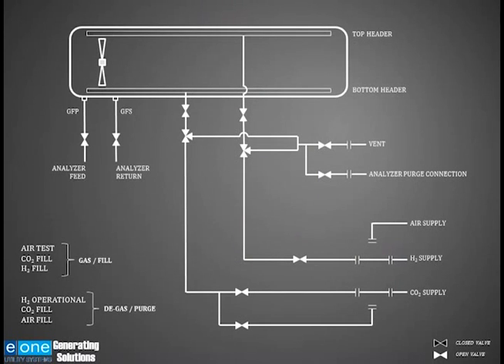Now I'm going to go through the purging process of the generator, and we'll make an assumption here that this generator was just worked on and it's got air in it, and now we want to put hydrogen in it. The key point here being that you don't want to put hydrogen in the generator while air is in there. So we want to put an inert gas to get rid of the air. So the first step that we're going to do is pressurize the generator.